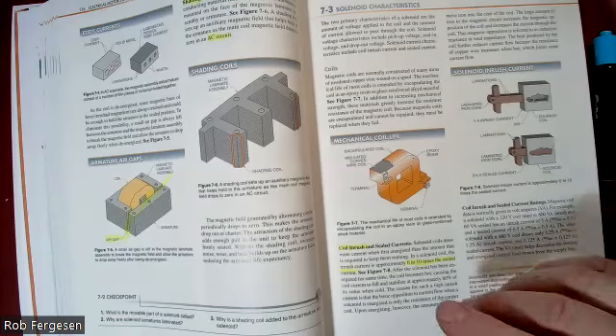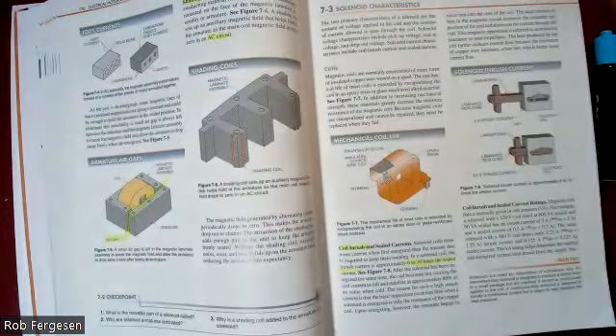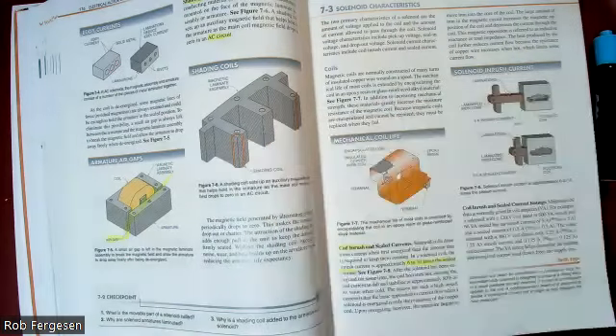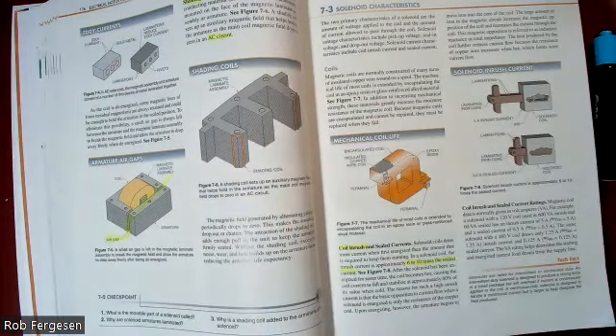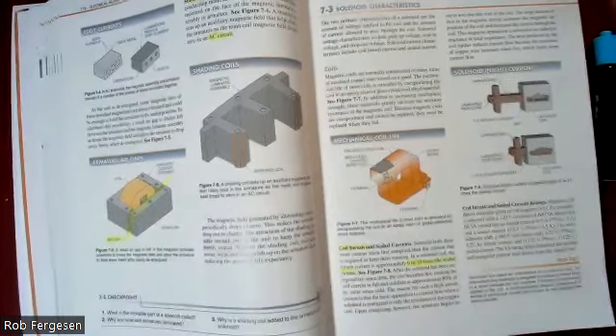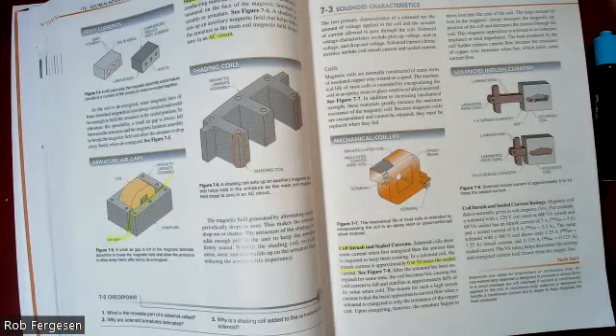for AC circuits. In an AC circuit, the current basically drops to zero every 1/60th of a second. So by using a shading coil, it creates an extra time frame where you're maintaining your magnetic field, and keeps that coil against it, enabling your magnetic circuit to continue even when every 1/60th second there's no current. That's a very important feature. If that breaks, you're going to get chatter. It's going to chatter at basically 60 cycles per second, which is what AC electricity is in the US. So that's an important concept.